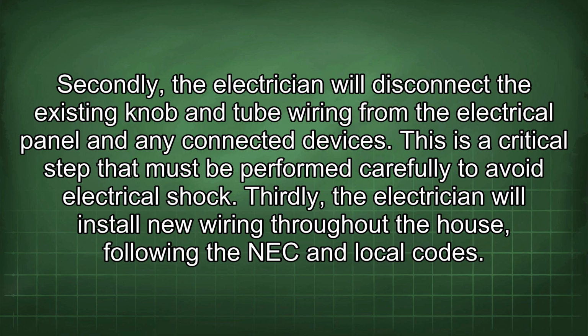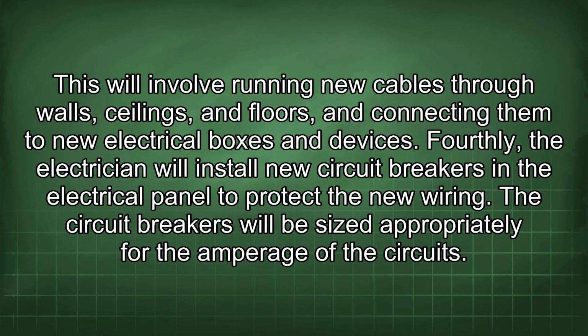Thirdly, the electrician will install new wiring throughout the house following the NEC and local codes. This will involve running new cables through walls, ceilings, and floors, and connecting them to new electrical boxes and devices. Fourthly, the electrician will install new circuit breakers in the electrical panel to protect the new wiring. The circuit breakers will be sized appropriately for the amperage of the circuits.